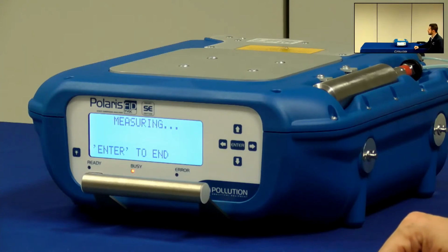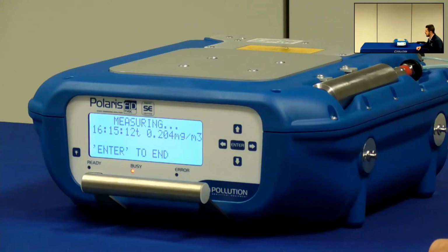In this case, I selected a 50 milligrams method and I'm using the integrated 1 liter zero air cylinder. I could also use an external gas tank, or in other methods, there is the possibility to use ambient air as zero air.